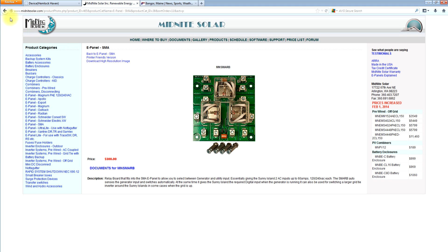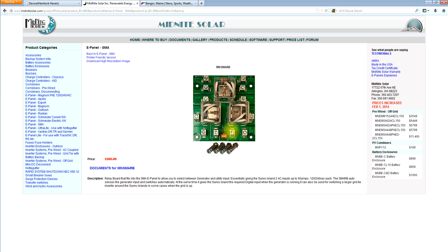For any inverter that has a single input and you want dual inputs. There's a little terminal block down here and there's some jumpers right here. So what you can do is you can put the jumpers on, and the SMARB relays will actually be powered by the inputs from the generator. Or you can move the jumpers down and you can power the SMARB relay coils by the orange terminal block with an external source.